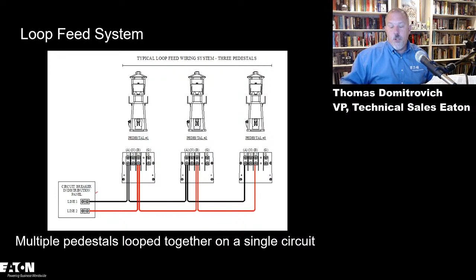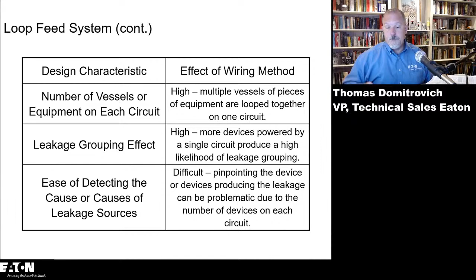You can put these in a loop. There's benefits for a loop. You can have the effective wiring method, with more devices powered by a single circuit. The problem is trying to pinpoint the device or devices that produce the leakage currents that cause the problem, because it's a string basically. If one has a problem, you take them all out.